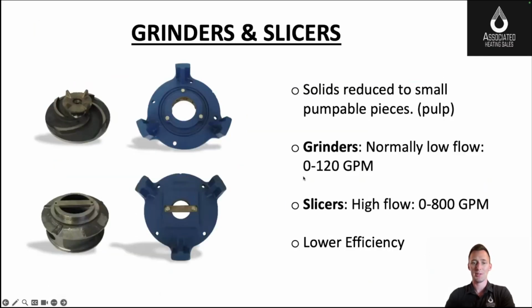Some other options that you see on the market, starting with the bottom one actually, is a slicer. We really like these. No big issues here because they're typically paired with a double seal pump, high horsepower, high flow, these slicers do quite well. The grinders do okay, although I will say an undersized grinder is the one that we get the most calls about. It's clogging on items, it wraps things up. The idea here is that this grinder apparatus sits at the opening of the pump or the entry of the pump and grinds up sewage to a more pumpable size.